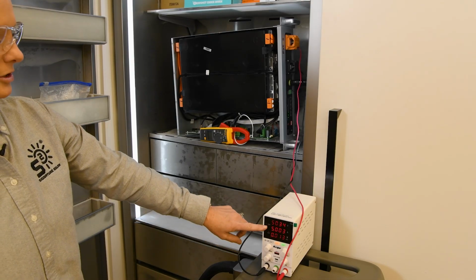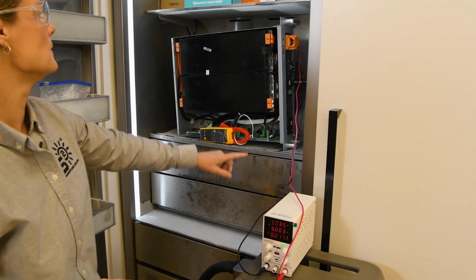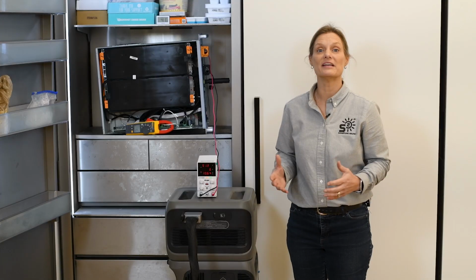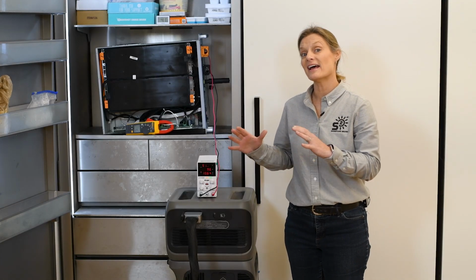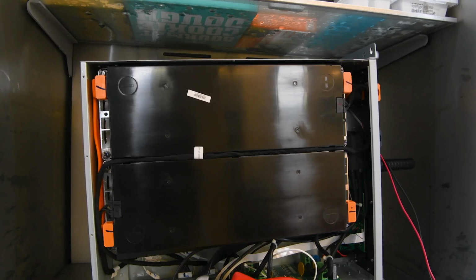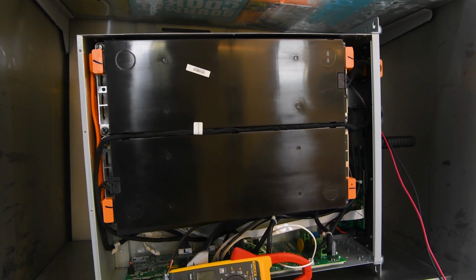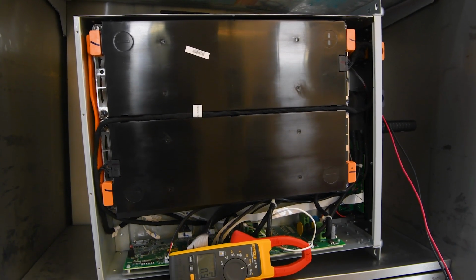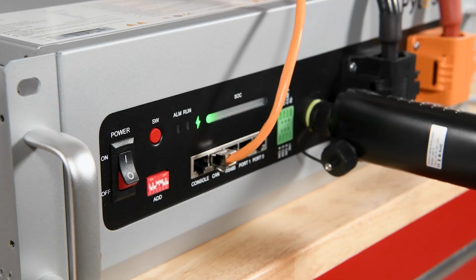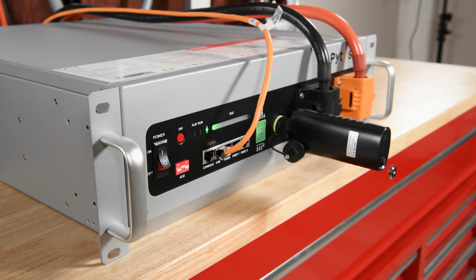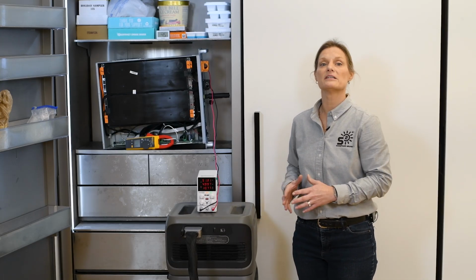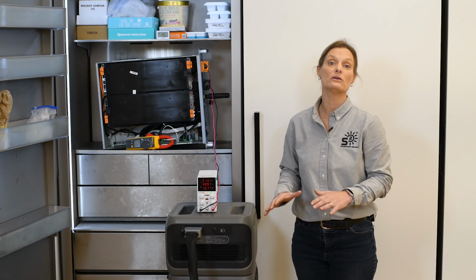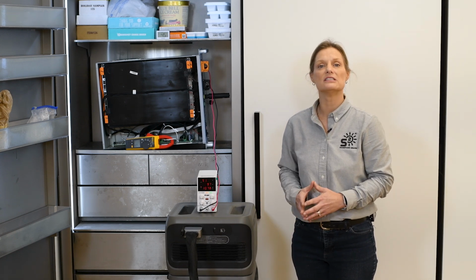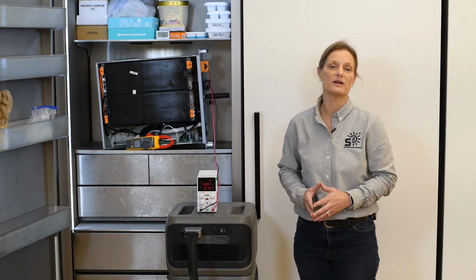The battery is still receiving a steady 5-ish amps from the power supply, allowing it to continue charging even as the temperature drops. This feature is essential for colder climates where freezing temperatures can degrade lithium iron phosphate cells, potentially shortening their lifespan. To protect the battery, the BMS will shut down if the cells get too cold, pausing operation until temperatures return to a safe range.